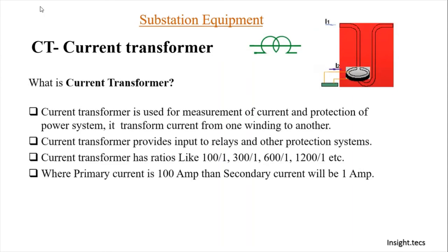So what is a current transformer? Current transformer is used for the measurement of current and protection of power systems. It transforms current from one winding to another and comes in various ratios like 100 ampere to 1 ampere, 300 ampere to 1 ampere, 600 ampere to 1 ampere, and so on. This means that when the primary current is 100 ampere, we will get 1 ampere in the secondary side.